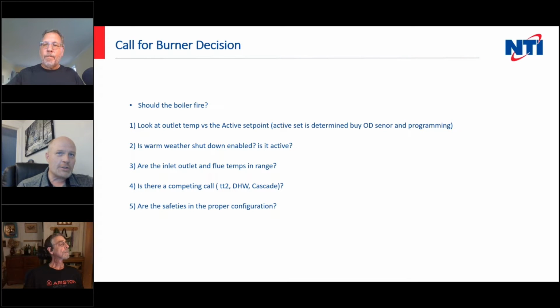So you need to be 100% sure you know which one the boiler is responding to, because if it's responding to a call for heat that requires 80 Fahrenheit, and you're expecting it to call for heat and you want 180, you're going to be disappointed. So your outdoor sensor affects your active set point in most cases. Warm weather shutdown, this one caught me this past winter. I spent probably 30 minutes troubleshooting before I realized that they had enabled a warm weather shutdown. You get tunnel vision, you think there's a problem, and of course it just turns out the boiler did exactly what we told it.